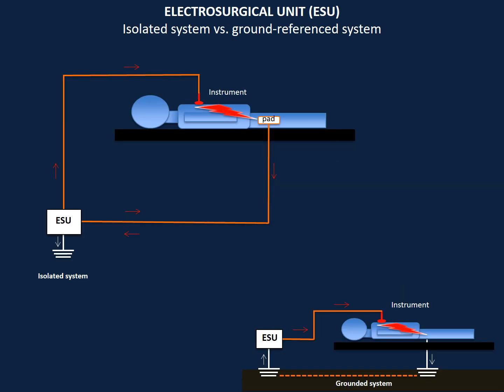The electrosurgery unit requires the presence of a circuit for current to flow. When using a monopolar instrument, the circuit is composed of the generator, which is the source of the electron flow and voltage; the instrument, which acts as the active electrode; the patient; and the patient-return electrode. The current flows between the electrodes through the patient's body, and generates the required heat for the electrosurgical effect.